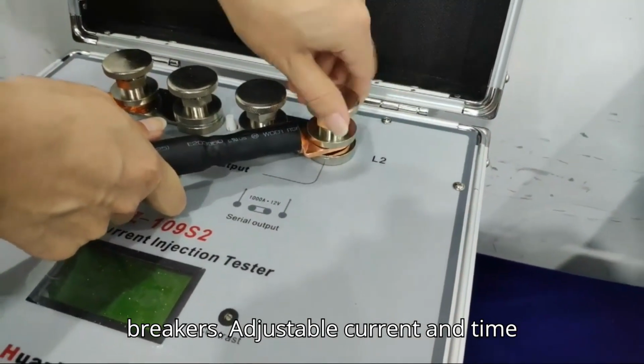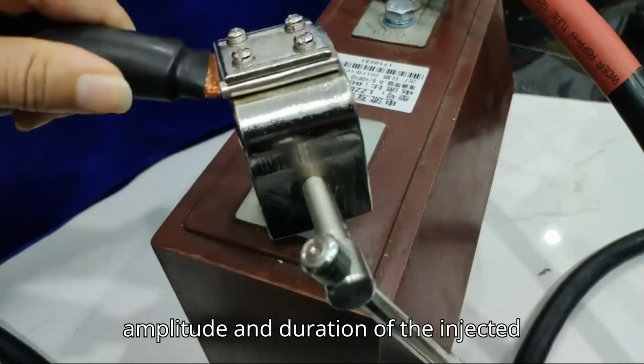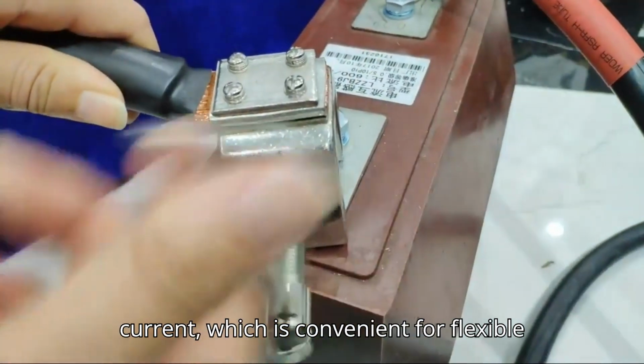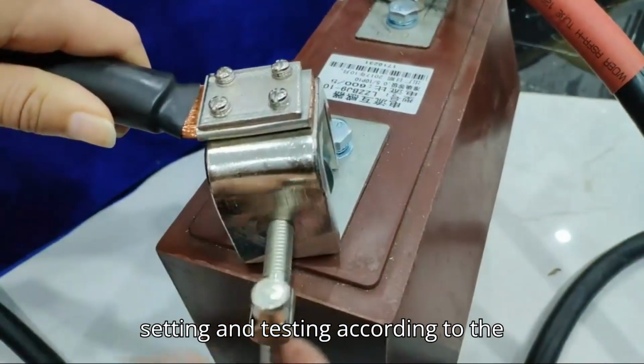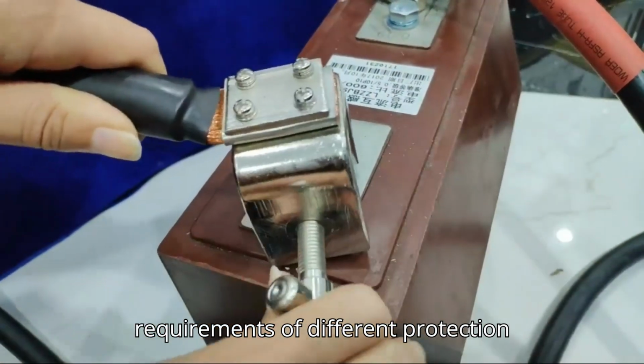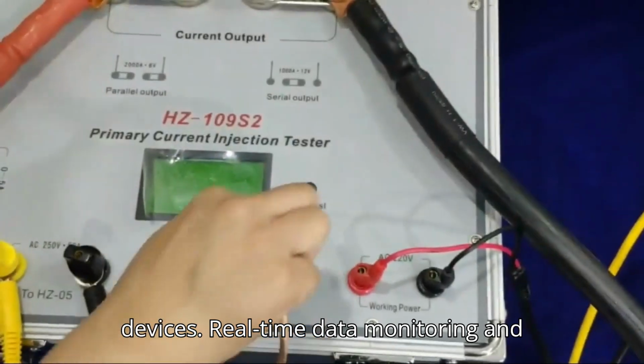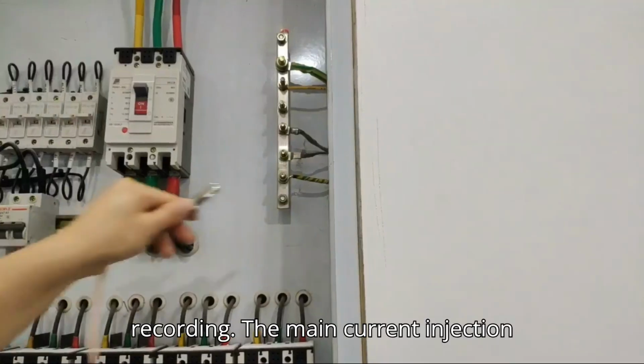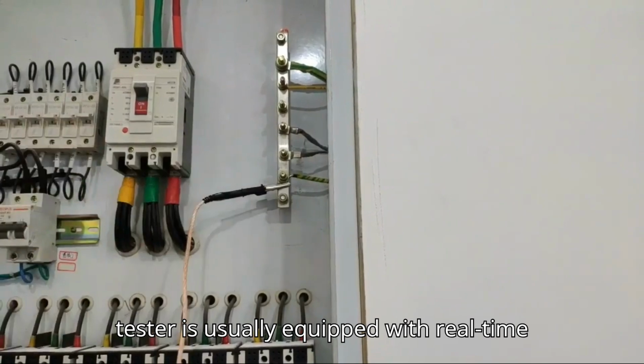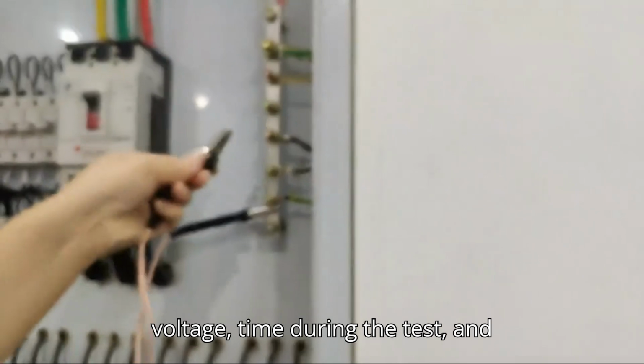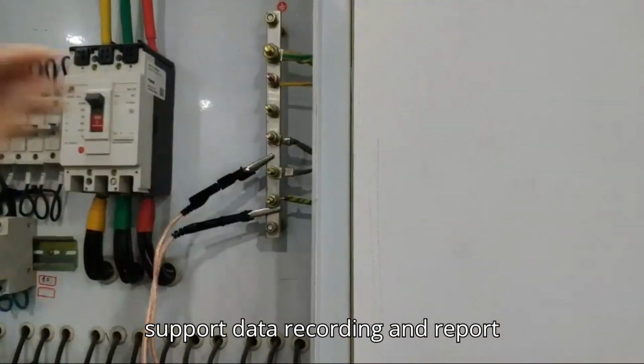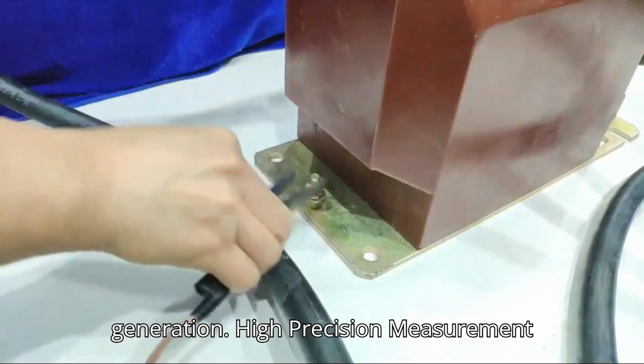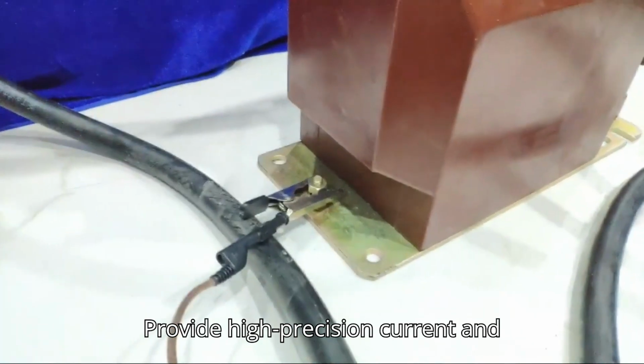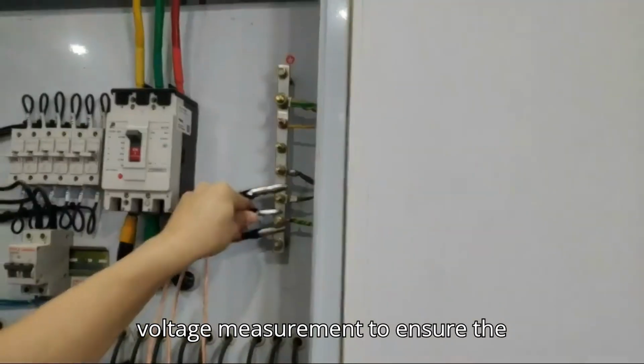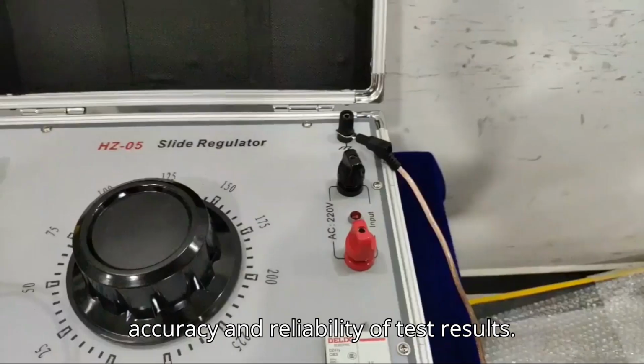Adjustable current and time settings. The tester can adjust the amplitude and duration of the injected current, which is convenient for flexible setting and testing according to the requirements of different protection devices. Real-time data monitoring and recording. The main current injection tester is usually equipped with real-time data display function, which can display important parameters such as current, voltage, time during the test, and support data recording and report generation. High-precision measurement. Provide high-precision current and voltage measurement to ensure the accuracy and reliability of test results.